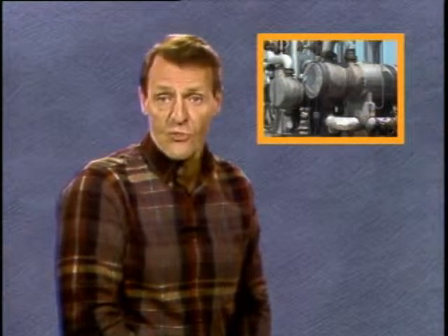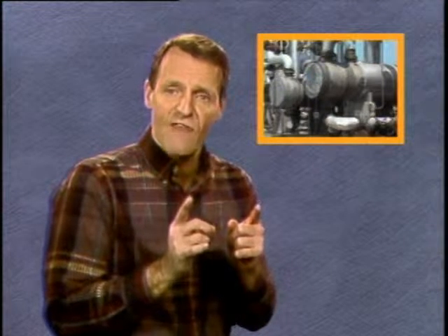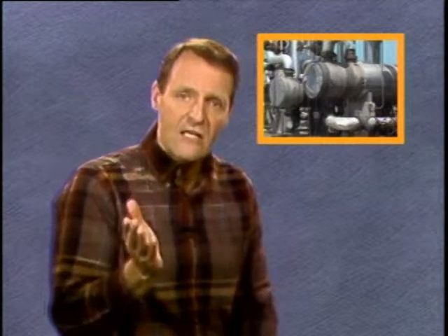When air, non-condensable gases, or other vapors are trapped inside a heat exchanger, they can prevent the unit from operating efficiently. This is because the air or gas can either blanket the tubes or block the tubes off and prevent fluid from flowing through them. The effect is the same as the effect created by fouling. Less heat can be transferred across the tubes.